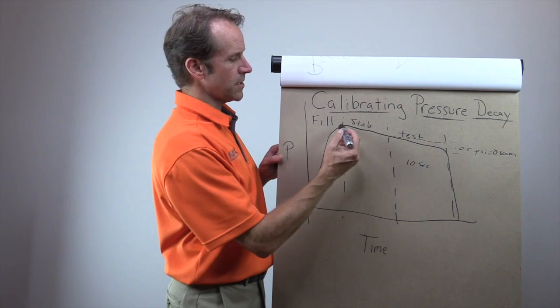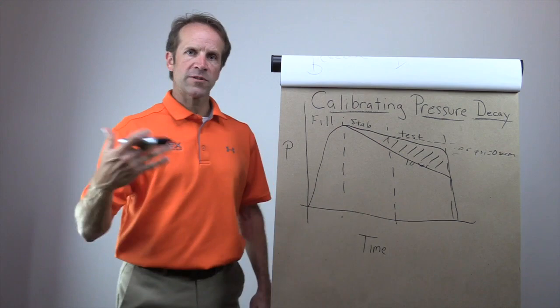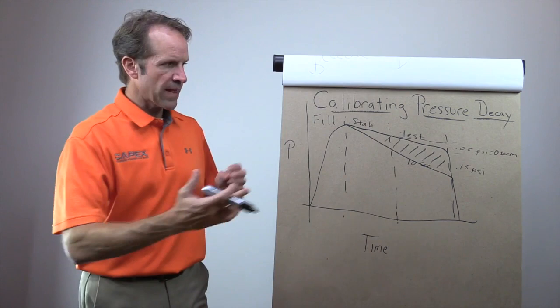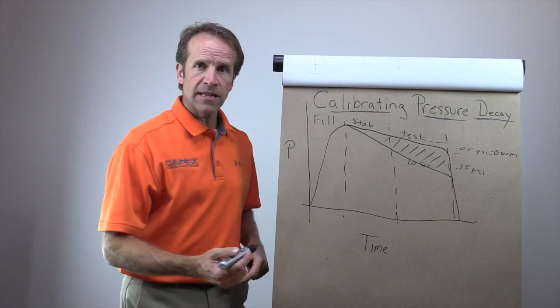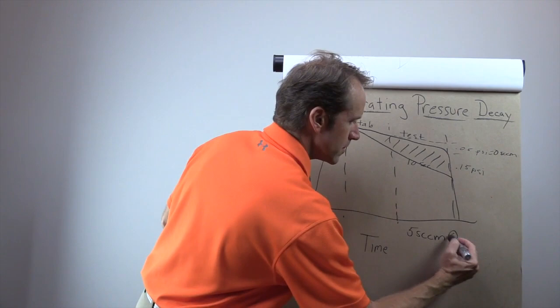So this might be the curve, how it looks with the leak standard introduced. Again, same part. So the leak standard is going to have greater pressure loss. So that space there represents greater pressure loss. So let's say that equals 0.15 psi over that 10 seconds versus 0.05 psi over that 10 seconds.